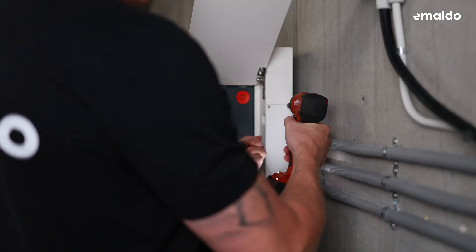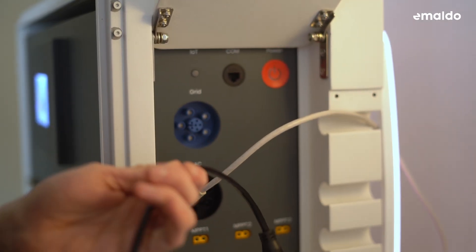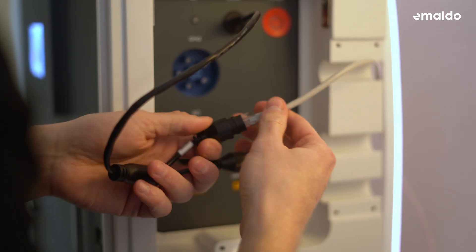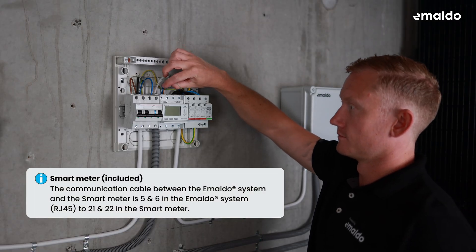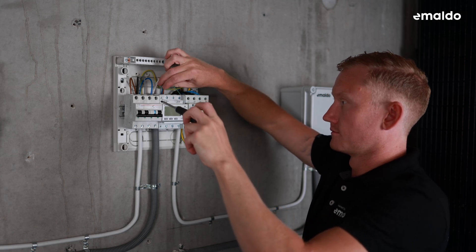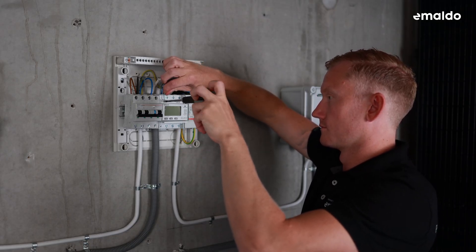Begin by unscrewing the side plate. Continue by wiring the RJ45 smart meter communication cable into the Y splitter labelled with meter. You also have the option to connect an ethernet cable by using the LAN port on the Y splitter. Ensure the wiring is identical on both ends of the cable at the RJ45 plugs. Connect the cable to the COM port on the Emaldo power system. The communication cable between the Emaldo system and the smart meter is pins 5 and 6 in the Emaldo system to pins 21 and 22 in the smart meter — 5 always goes to 21 and 6 to 22. We recommend using a CAT6 shielded cable or better. For further details, refer to the user manual provided with the smart meter.